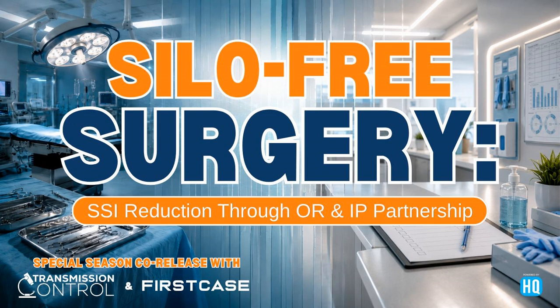And that's a term that I think piques a lot of ears, worst case scenario. Is there an objectively defined worst case scenario? No, nothing is out there that specifies what is worst case. They give you, like I just mentioned, reduced soak times, reduced flushing times, detergent dosage, and the amount of soiling that you put on the product. So you're just overcompensating on the soiling and undercompensating in the processing. That's it. But where you cut that, it doesn't specify anywhere. We just know from the instructions what we need to put down. Anything that affects the processing are the steps that we will minimize. Yeah, and that makes sense.